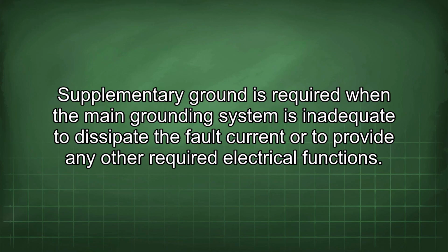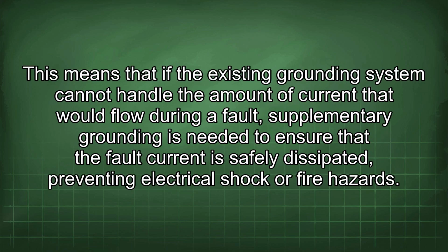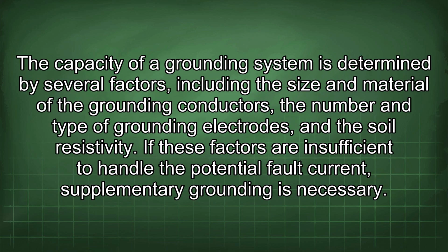Supplementary ground is required when the main grounding system is inadequate to dissipate the fault current or to provide any other required electrical functions. This means that if the existing grounding system cannot handle the amount of current that would flow during a fault, supplementary grounding is needed to ensure that the fault current is safely dissipated, preventing electrical shock or fire hazards. The capacity of a grounding system is determined by several factors, including the size and material of the grounding conductors, the number and type of grounding electrodes, and the soil resistivity.